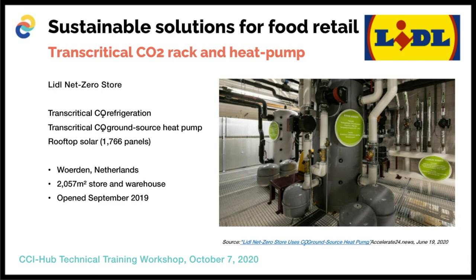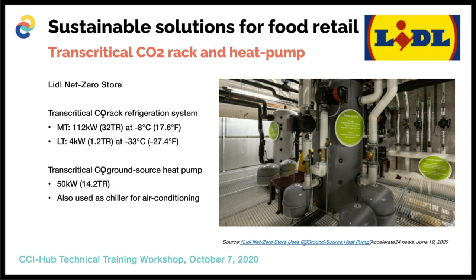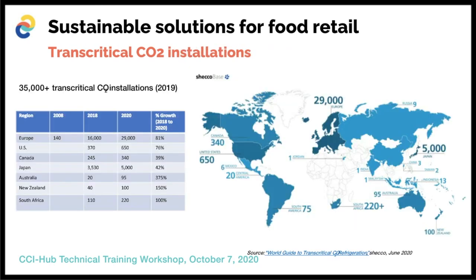Some more technical details. As I mentioned, we'll be sharing the slides afterwards with all delegates so you can access this technical information. It's important to mention that the CO2 system is used also as a chiller for air conditioning. So we see that one system can cover all the thermal needs of a retail facility. To sum it up, for CO2 transcritical, including the large capacity installations in industrial refrigeration, there are more than 35,000 facilities equipped with CO2 transcritical by 2019. So there is a fast growing market around the world for CO2 transcritical.